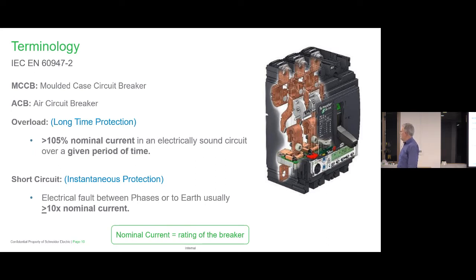Okay, terminologies. These are all pretty simple, and I don't need to go through them too much, but all I would say is that the nominal rated current of a circuit breaker is the starting point, IN. So that's the first thing you look at when you go to a breaker or you want to select one, that you need to know what the nominal rating is. And the overload protection, anything greater than 105, it's in an overload state. It's going to trip at some point, okay? Instantaneous. Earth fault between phases and earth can be up to 10 times the nominal rated current. Sizable. It's a major amount of current that these protection devices have to be able to withstand.